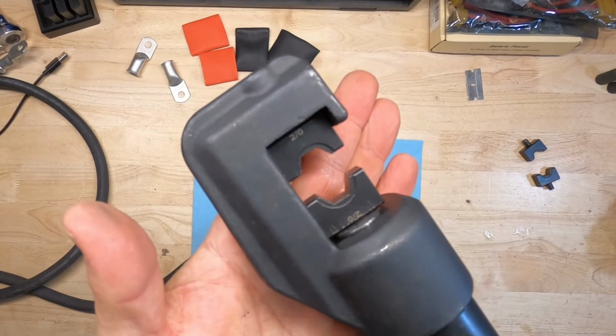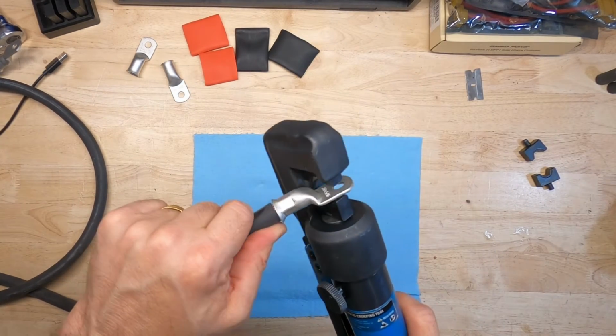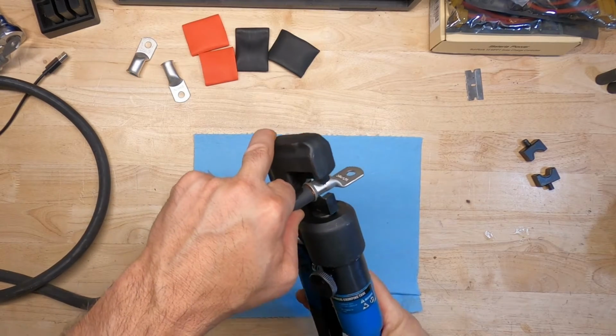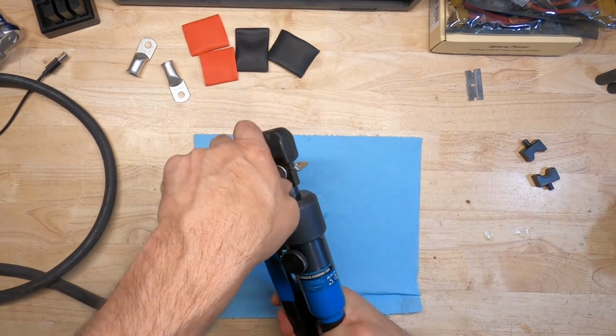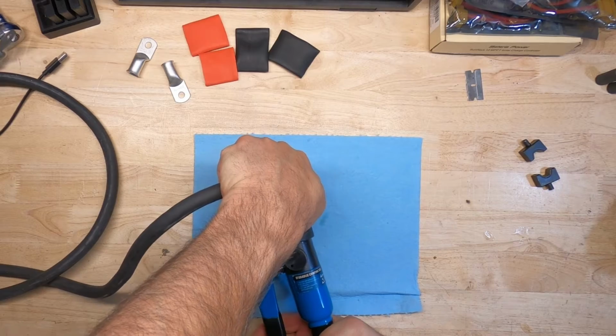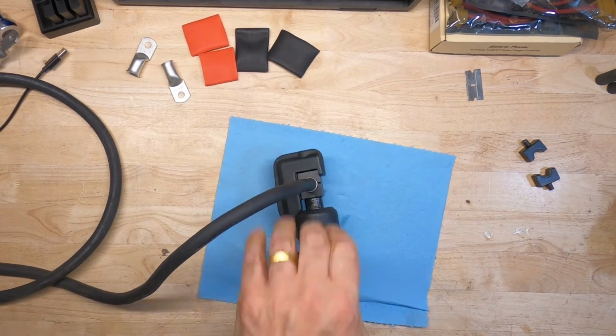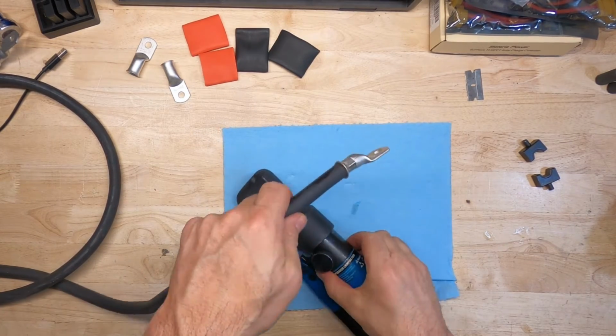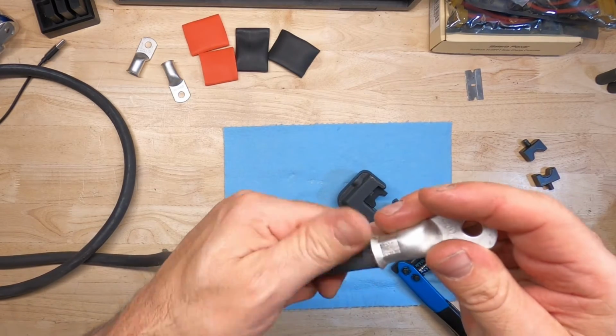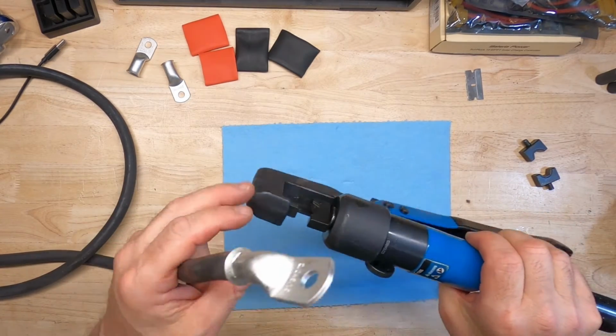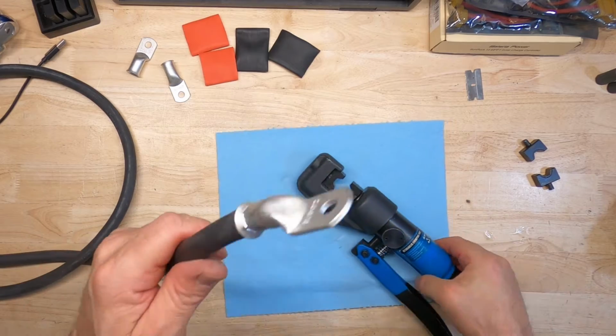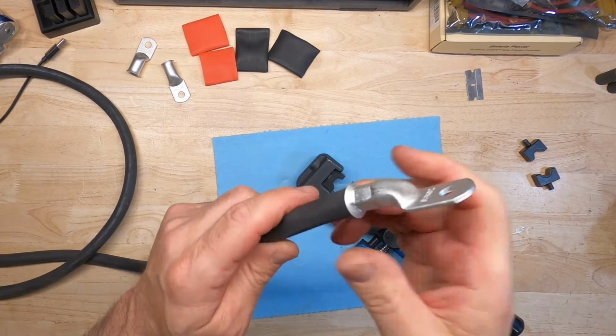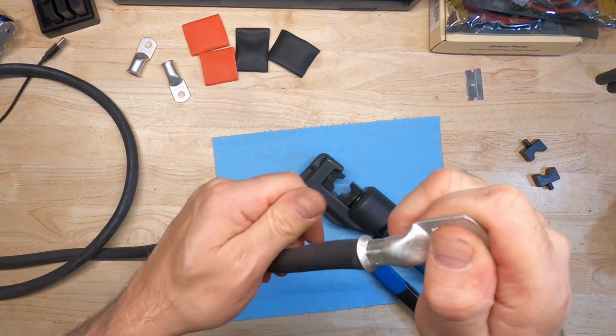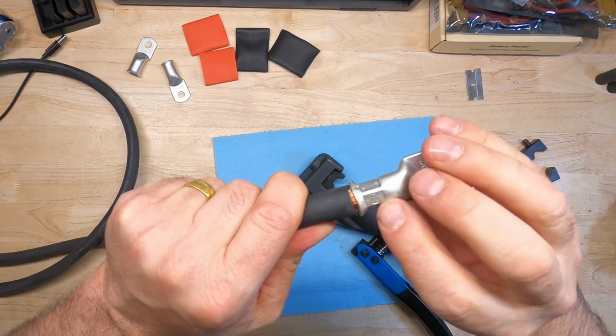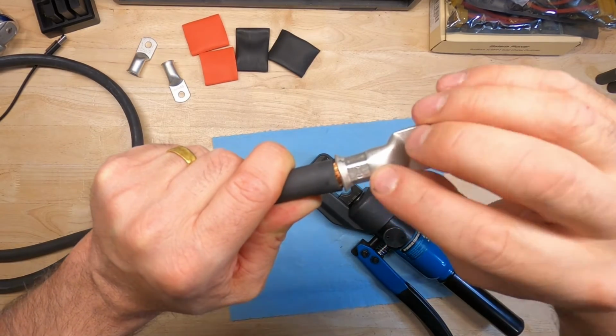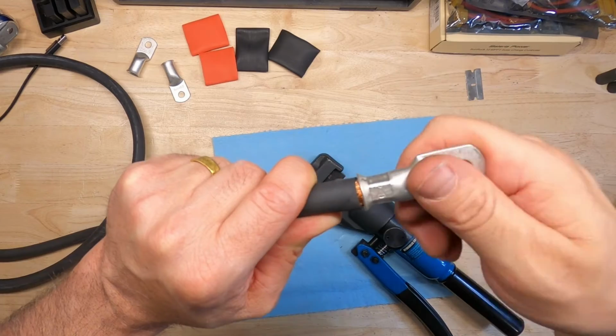Now we got our 2-aught in there, and this is where we're really going to bite down on it. See, it's starting to leak. Gotta be really careful with this thing. I don't know how long those O-rings are gonna last. Anyway, that is a really solid crimp right there. If you can see the indentation in there, see it says 2-aught? That means it's tight enough.